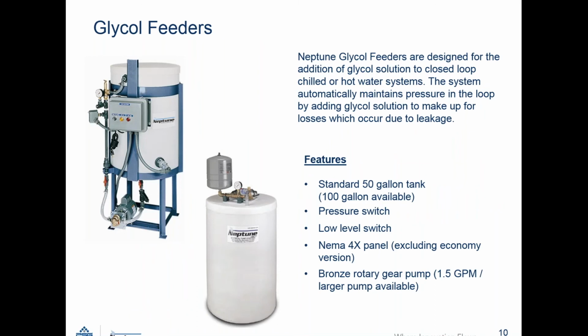Glycol feeders. Glycol feeders are designed to add glycol solution into a closed loop, chilled or hot water system. It automatically maintains pressure in the loop by adding glycol. When leakage losses happen in the system, the glycol feeder can replenish that leakage to restore the pressure in the system.